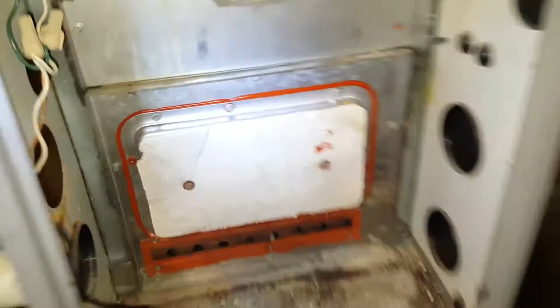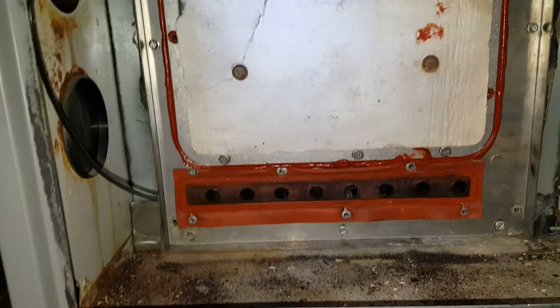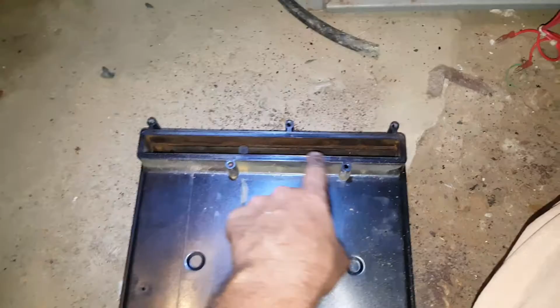So the exchanger is in, married to the old exchanger, with our primary connection to the secondary. That collector is back together, so that outlet on the bottom is the secondary's outlet. That outlet goes here to this collector box on the back side, where we're gonna seal these two points, and then the inducer motor goes onto that. Now the collector is on.